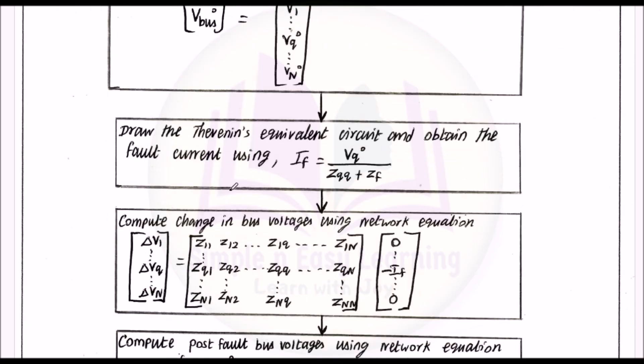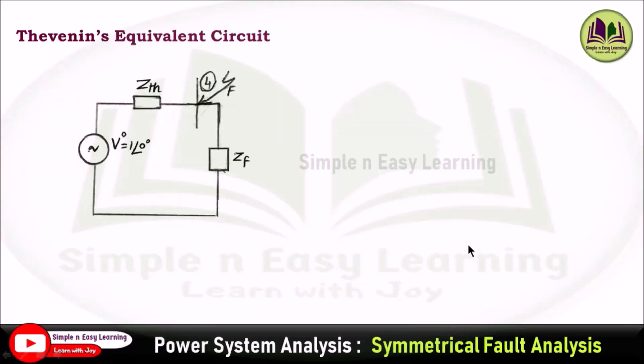The next step: draw the Thevenin equivalent circuit and obtain the fault current using the corresponding formula. For the given single line diagram, after analyzing the reactance diagram, we draw the Thevenin equivalent circuit to find the fault current. The fault location is at bus 4, with Thevenin impedance in series with the Thevenin voltage source, and the fault impedance Zf connected at the fault point.